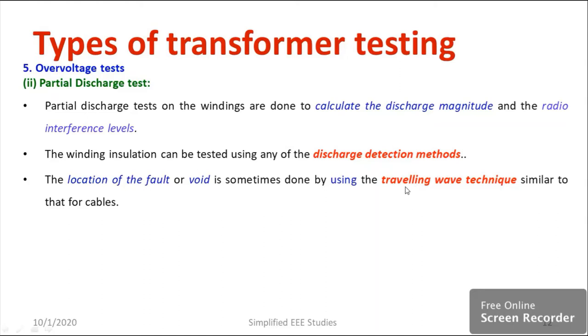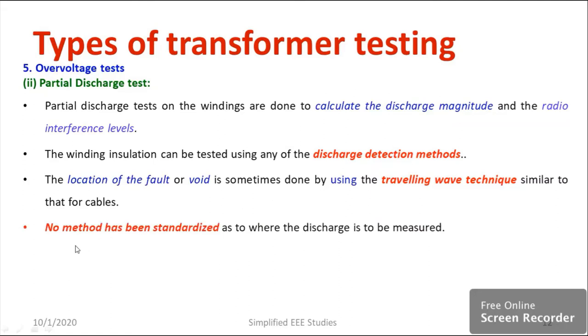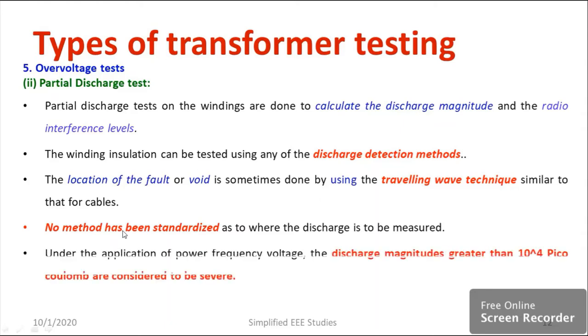You can refer to the previous video on cable insulation testing where traveling wave technique has been explained. The same can be applied for winding insulation. There is no standard method, so whichever method is convenient you can go for that. Under the application of power frequency voltage, discharge magnitude greater than 10^4 picocoulombs is considered as severe.